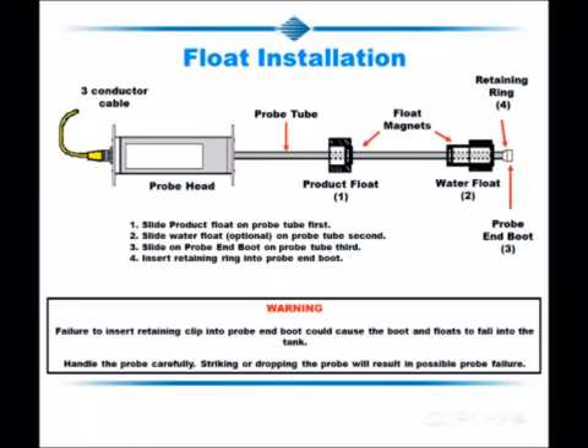The float installation. On the bottom of the float shaft is an end boot and a retaining ring. That plastic end boot is to insulate the metal of the probe from the metal of the inside of a tank. You remove the clip and remove the end boot. You would slide the product float onto the probe shaft with a magnet at the bottom. Slide the water float on the probe shaft with a magnet at the top. Reinstall the end boot and the retaining ring.